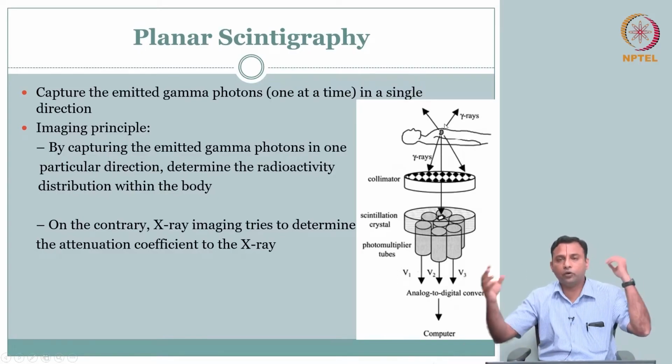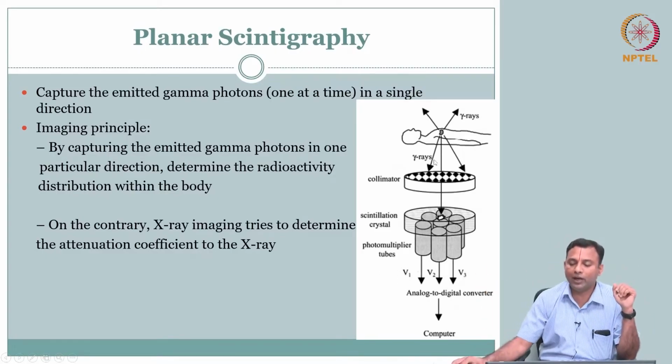The gamma rays can go in any direction. So typically you have a detector, and the detector is going to catch the different gamma rays. Again the same idea, line of sight. So you want a collimator so that you can eventually say where it is coming from. After the collimator, gamma rays directly cannot be captured, or you do not want that. What you want is a light signal. So the gamma rays interact with this scintillation crystal, which converts your gamma energy to visible light photons.